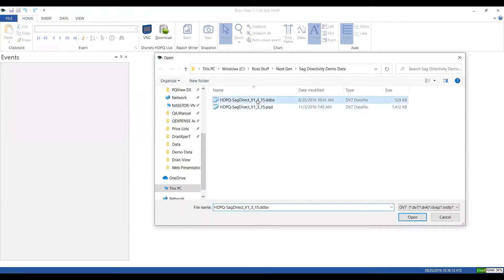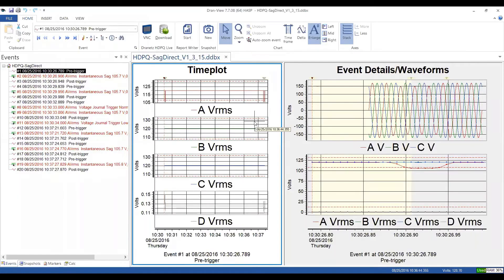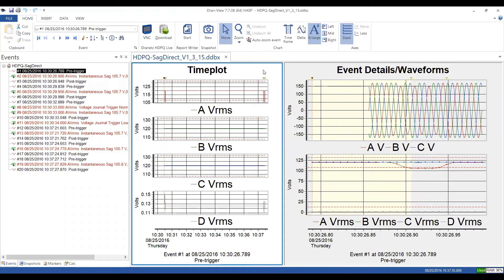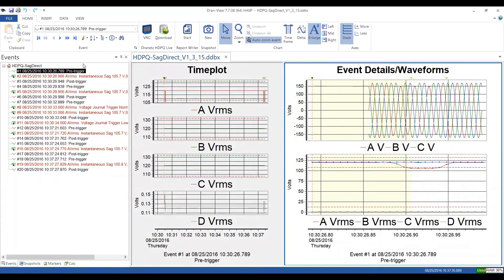Let me open up that file I had before — this is a demonstration file on SAG directivity. The DRANview interface is divided into three areas. The two right ones are called your viewing panes. You have your timeline, or history of monitoring pane, and you have your event details pane. This is a small test database, good for training because it doesn't have much data. It's a recording done with the HDPQ instrument to highlight our Answer Modules — specifically the SAG directivity Answer Module, which tells you the direction of a SAG.